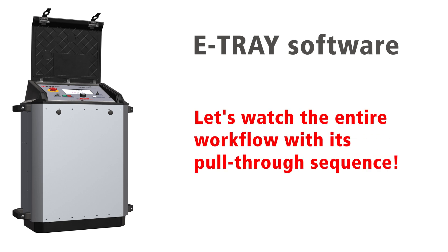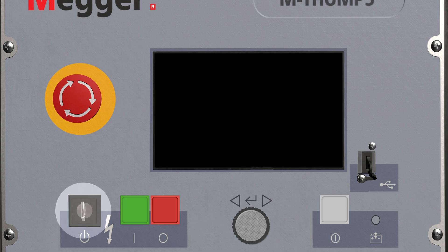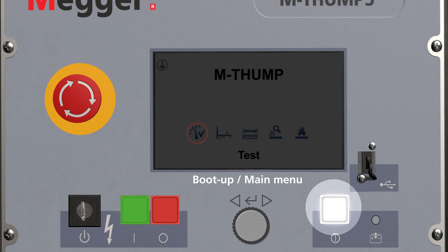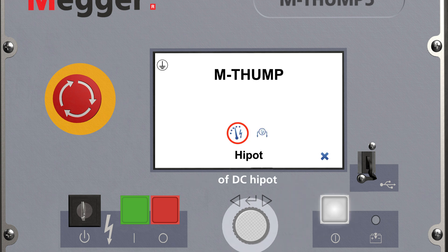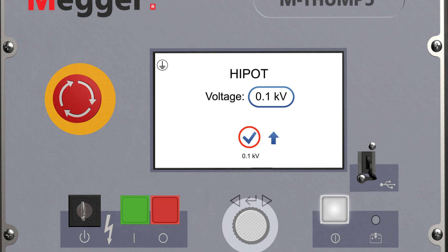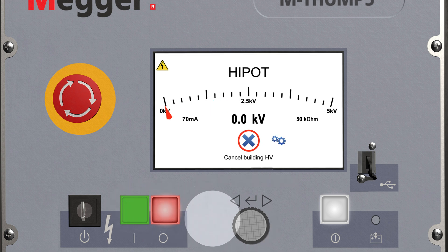Let's watch the entire workflow with its pull-through sequence. Turn the security key operated switch on. The system boots after you have pressed the power switch. Select and confirm the DC hipot test. Select the voltage set point for the DC hipot test. Set the duration of the test with the previously selected voltage. Ready to test. Confirm the high voltage initiation with the green button.